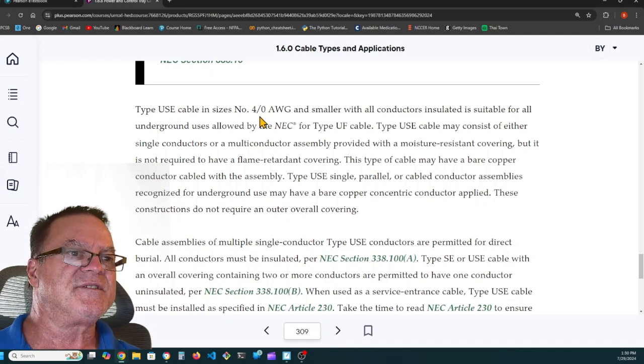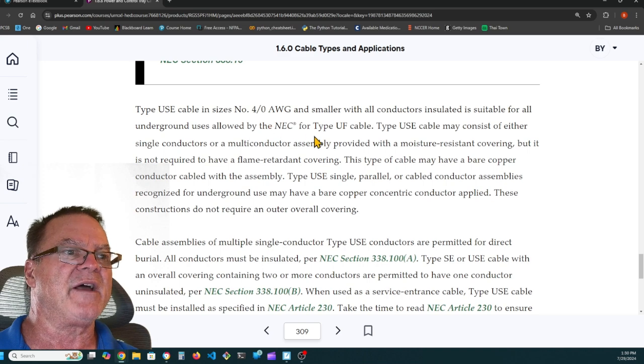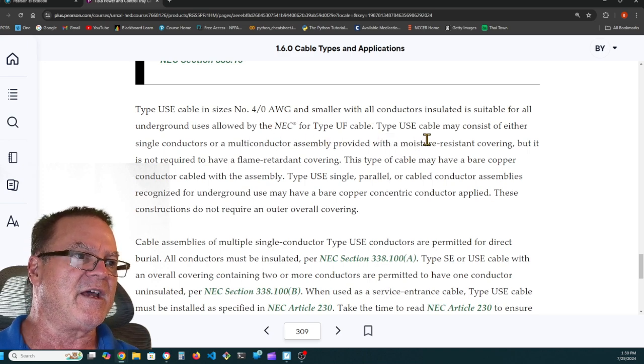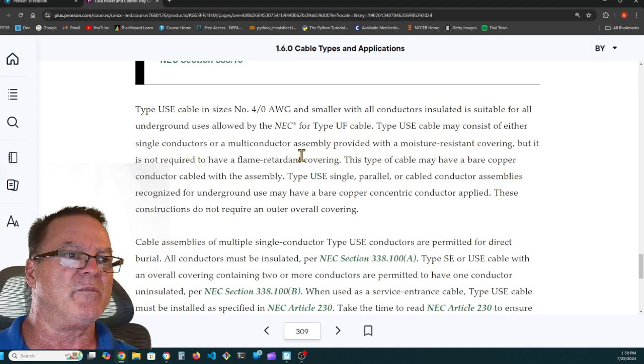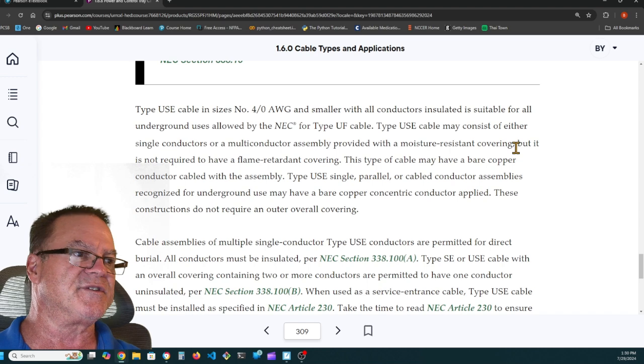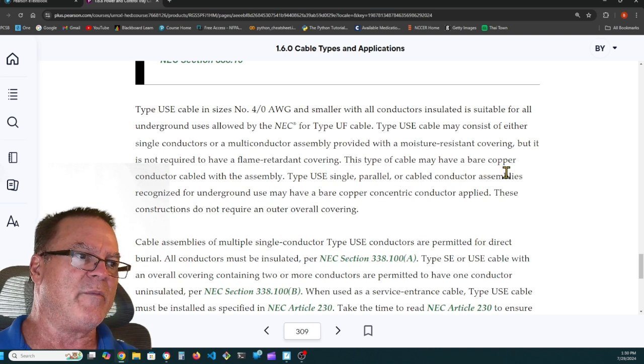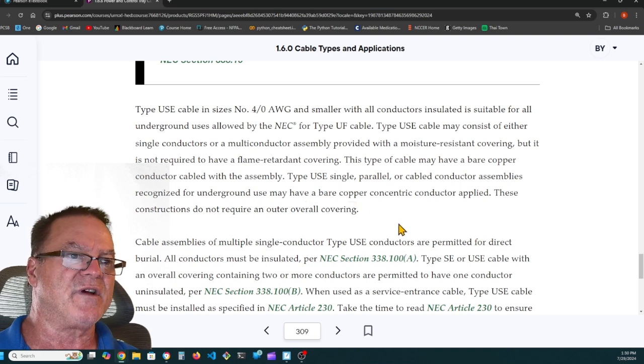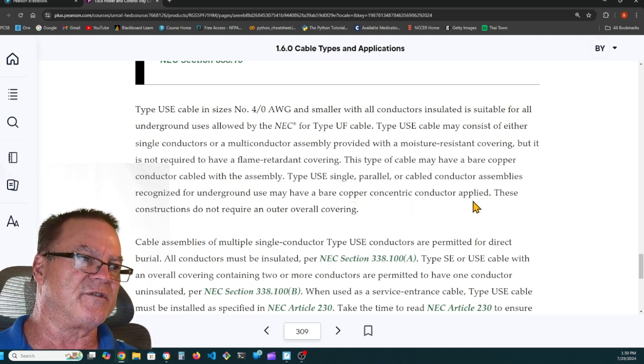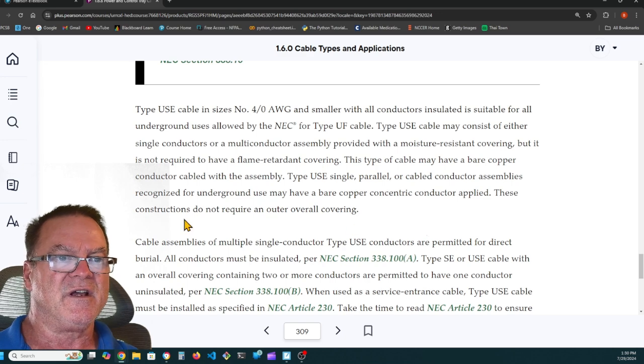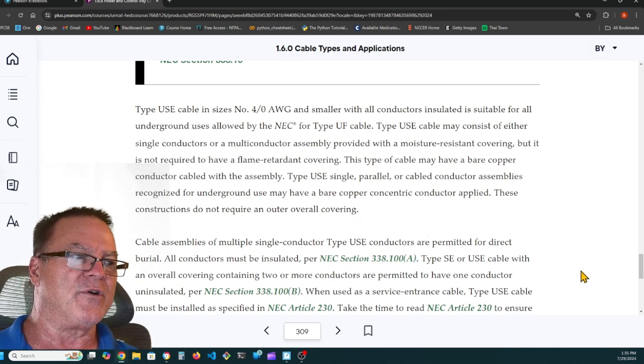Type USE cable in sizes from 4/0 gauge and smaller, with all conductors insulated, is suitable for all underground uses allowed by the NEC for type UF cable. Type USE cable may consist of either single conductors or a multi-conductor assembly provided with moisture-resistant covering, but it's not required to have a flame retardant covering. This type of cable may have a bare copper conductor cabled with the assembly. Type USE single, parallel, or cabled conductor assemblies recognized for underground use may have a bare copper concentric conductor applied. These constructions do not require an outer overall covering.